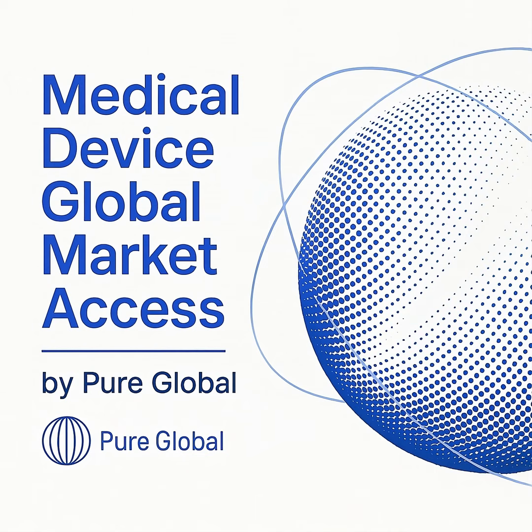The framework establishes 3 categories. Category 1 is for devices with the lowest risk, where the manufacturer can provide a clear justification that no HFE UE data is needed. This might apply to devices with very simple user interfaces, or those where use errors pose negligible risk to the patient or user.